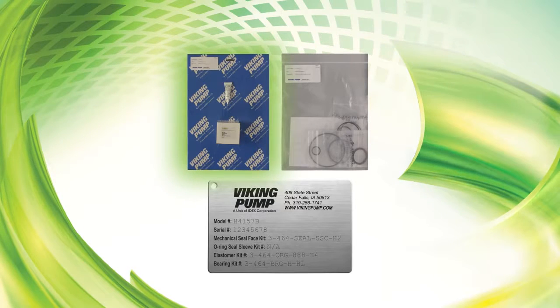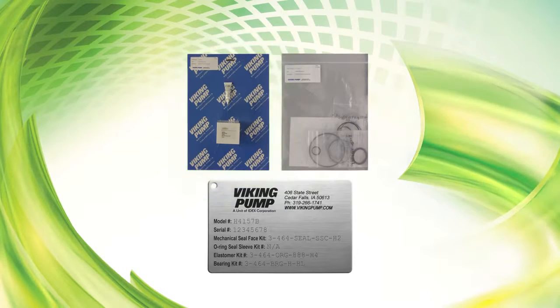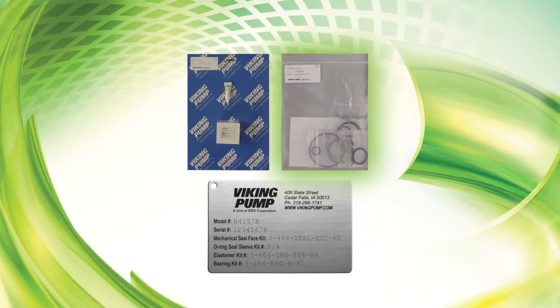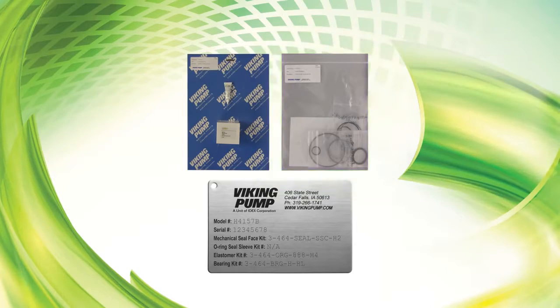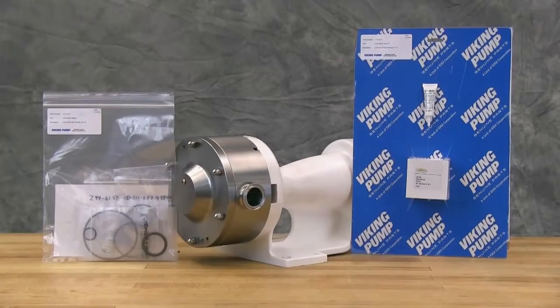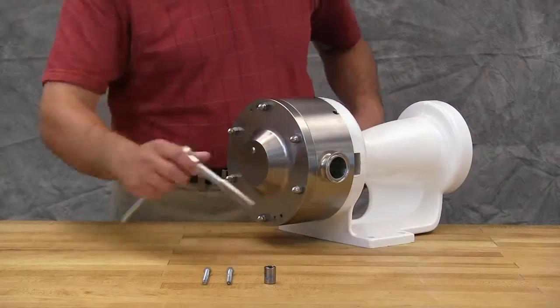The seal face kit includes the stationary and rotary seal faces, as well as the wave spring. The elastomer kit includes all of the O-rings needed for the seal, as well as the head, idler pin, and rotor retainer O-rings needed to reassemble the pump. The pumps covered in this video are Hygienic Series pumps with standard single mechanical seals. For additional information on installing double mechanical seals and O-ring seals, see the Technical Service Manual and our Hygienic Series seal installation videos. Remove the head nuts.